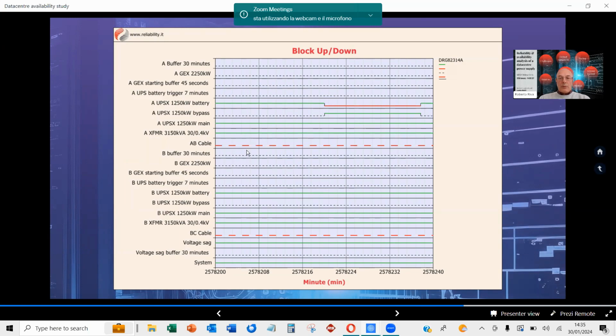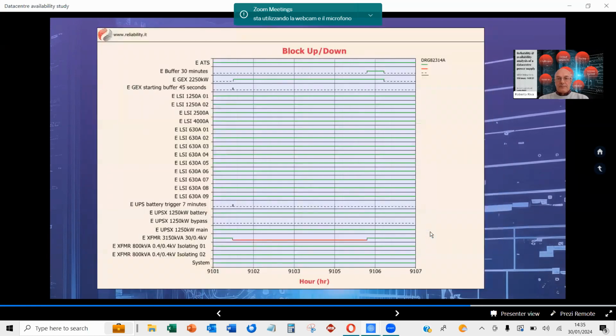And so we got a few things. So basically, we got a barbecue more than a data center. Now we have fire everywhere, and the system is still up and running. Obviously, we have a degraded system because some of the loads down at the far end are overloading. Okay, so within the window we are considering, which is this in minutes, we don't have any failure.